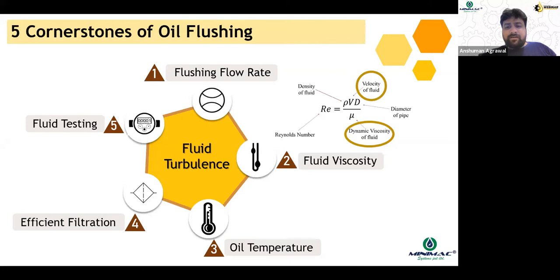The second cornerstone of flushing is fluid viscosity. For designing the fluid viscosity, again you refer to the same Reynolds number formula, because if you see the formula, there is viscosity in the denominator, and velocity, which is linked to the flow rate, in the numerator. So in order to decide what your viscosity should be and what your flow rate should be, you need to refer to the Reynolds number formula.